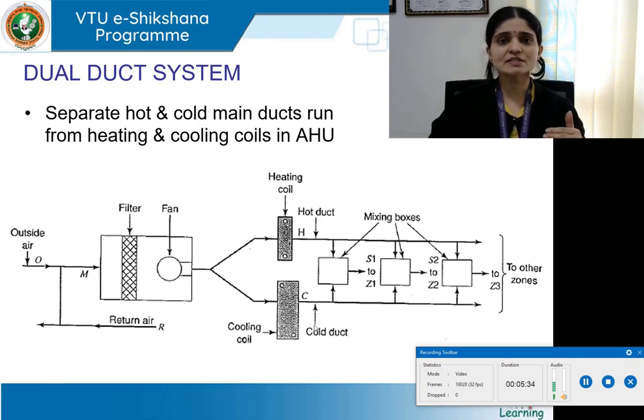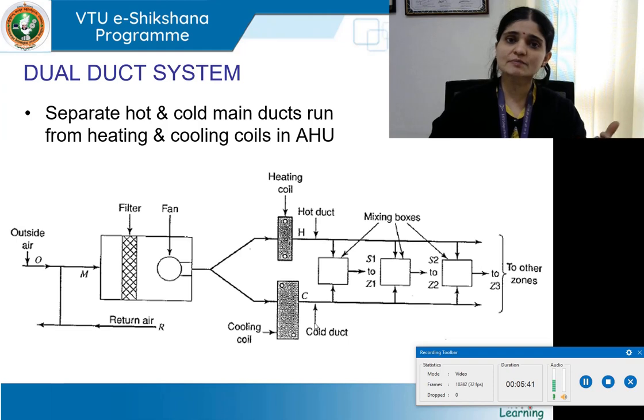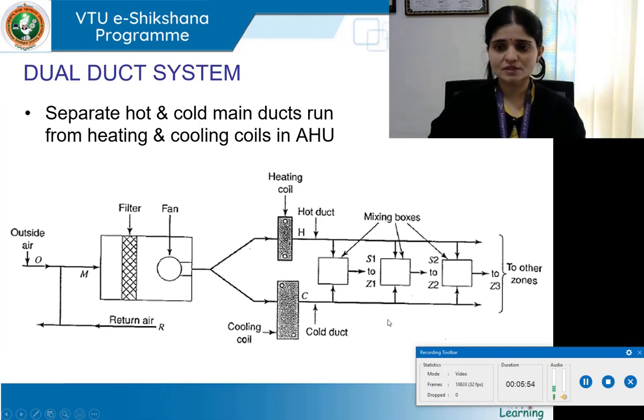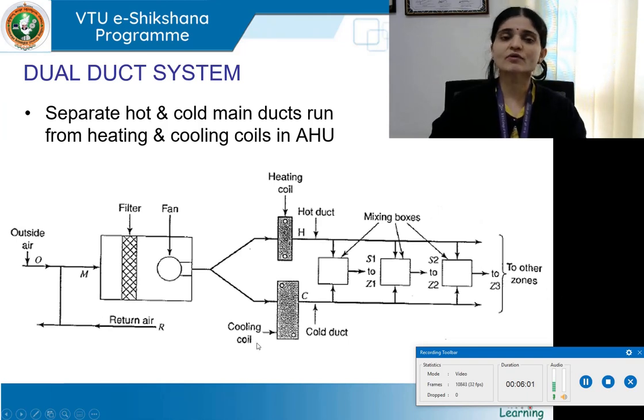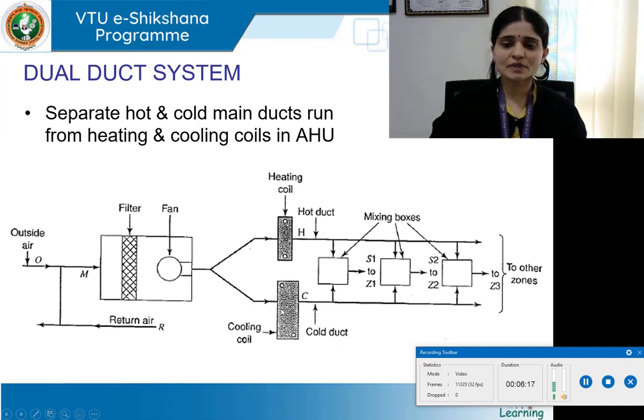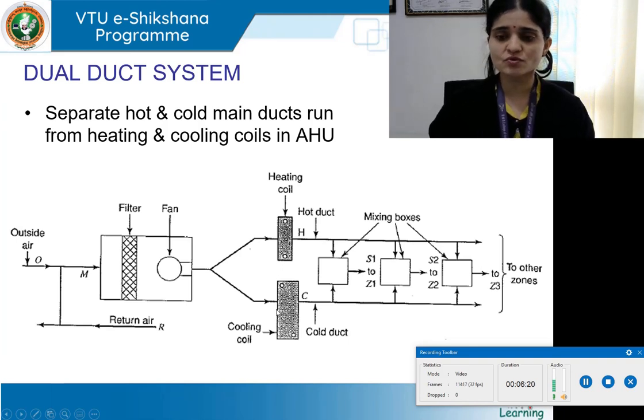If the objective is to cool the air, the mixed air passes through the damper and cooling coil. If heating is required during winters, it passes through the heating coil. The cooling coil leads to the cold duct (C) and the heating coil leads to the hot duct (H). These two ducts move ahead to mixing boxes, which serve various zones — zone 1 with its temperature, humidity, and air velocity parameters, and zone 2 with its own requirements — and then on to terminal AC units.